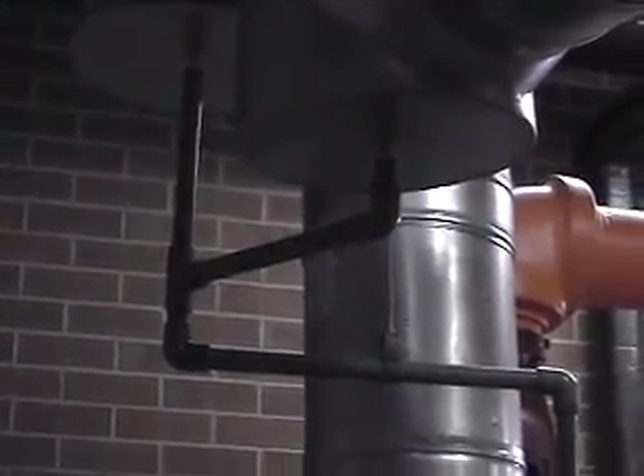We'll take rainwater. I mean, rain, melted snow, that can come back to the boiler and then just go out the drain line at that point. But we don't have drain tees here, so I would watch that. Just make sure that you're not getting any buildup in there. You see your drain tees up here where we're tying in the drain lines, because you're going to be raining in up top, and that's being run down to this same line, which is coming into this trap.